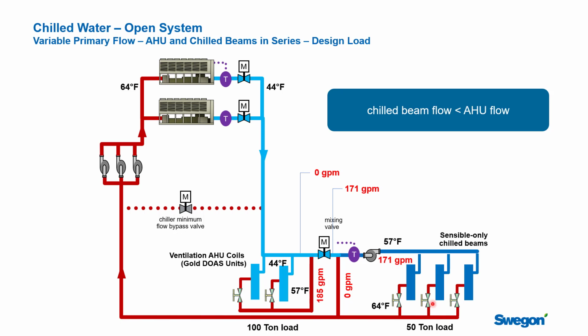So you really need to not just look at how the temperatures are going to work in your water system. You need to slow down and have a good look at your flow rates, and not just on a design day, but at, let's say, 50 and 25% load, remembering that these loads behave quite differently as the weather changes outside. And convince yourself that your flows are going to work well. Now, this system that we're showing you here is a good system. It does require this rule not to be broken. And for most cases, that's quite possible, but you do need to check your actual system design.